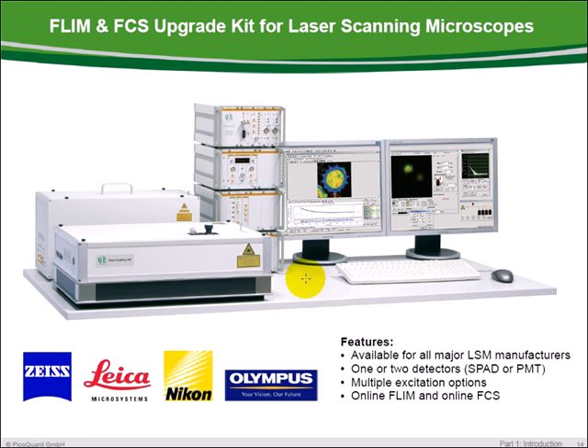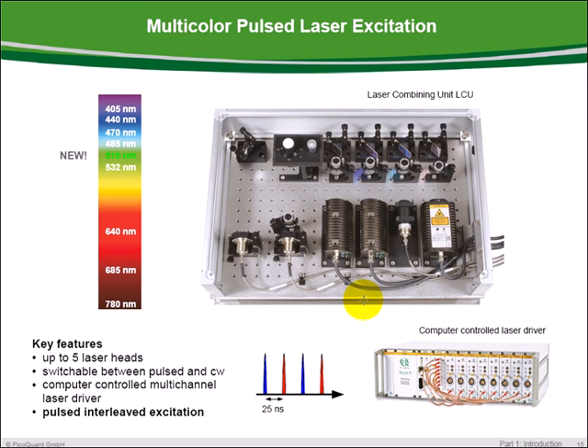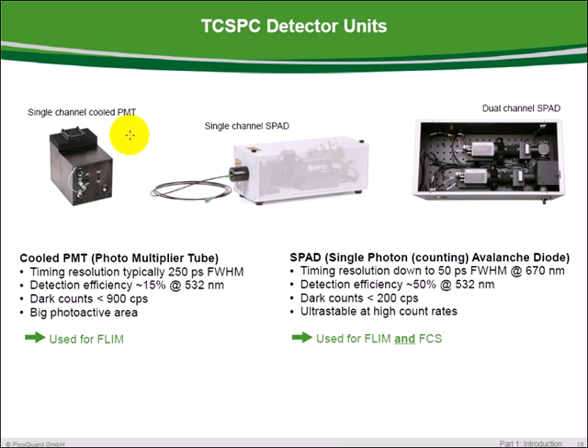The upgrade kit is available for all laser scanning microscopes of the major companies and is installed by PicoQuant as a turnkey solution. The upgrade kit is very modular and can be easily adapted to special needs. The pulsed lasers with adaptable repetition rate can be combined in a laser combining unit, and a broad range of lasers are available. The laser driver is software controlled, and different pulse sequences can be selected, such as pulsed interleaved excitation, exhibiting a pulse train with alternating colors. As time-resolved detectors, either PMTs or single-photon counting avalanche photodiodes, SPADs, are used. The SPAD achieves a detection efficiency of around 50% in the green wavelength range, together with excellent timing performance down to 50 picoseconds at 670 nm.